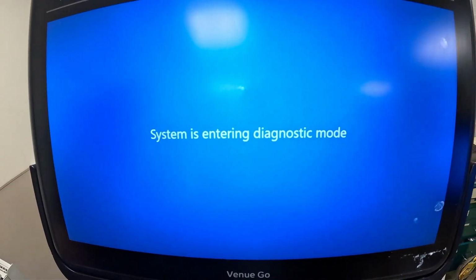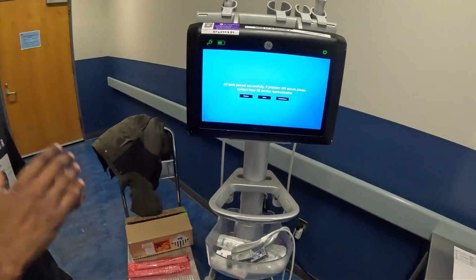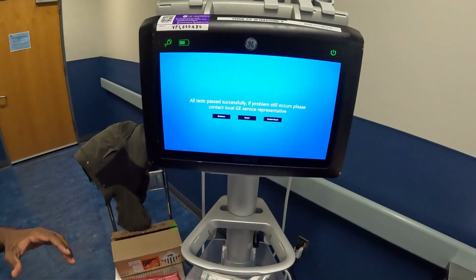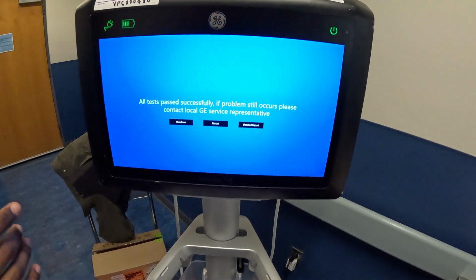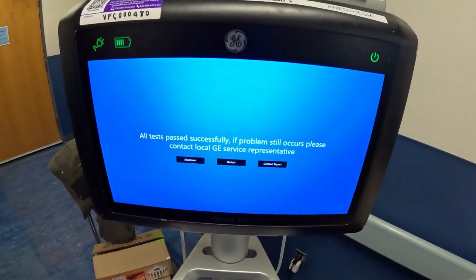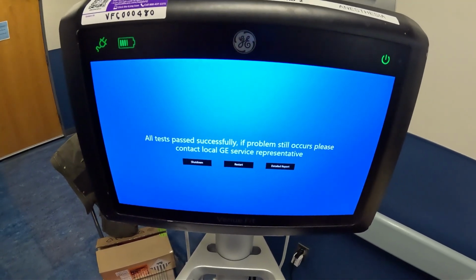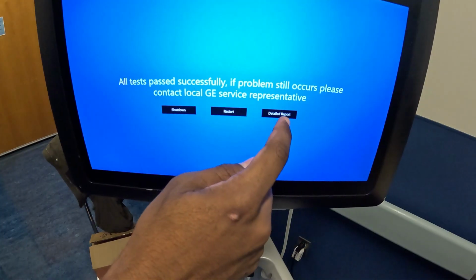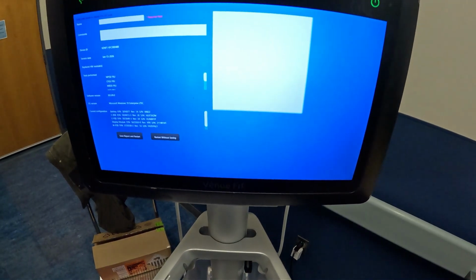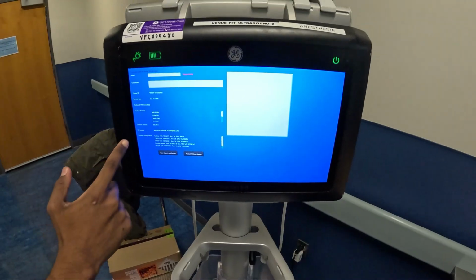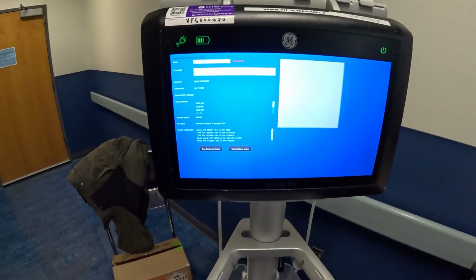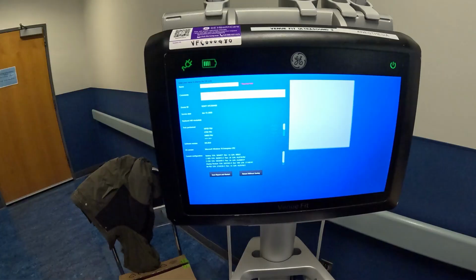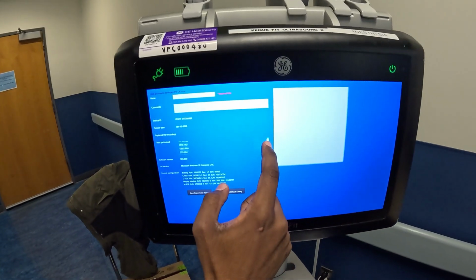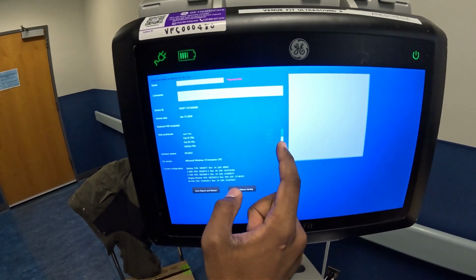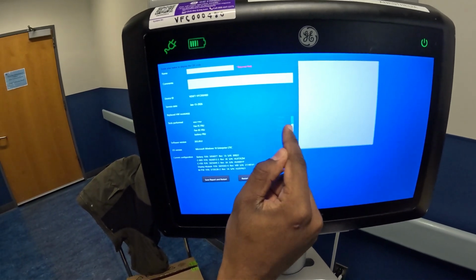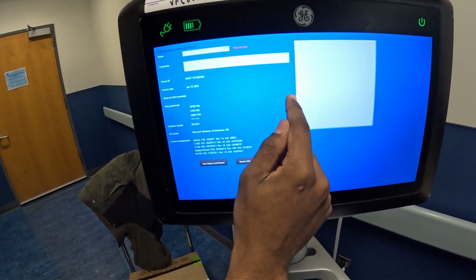System entering diagnostic mode. Once the diagnostic test has been completed, you want to see this screen which says all tests passed successfully. If problem still occurs, please contact local GE service representative. And you want to go to detailed report to see what tests were done, if the software version has been updated, which it looks like it has, and you want to slide this down to see that all tests have passed. And if they have passed, you'll see a green passed right over here to the right.